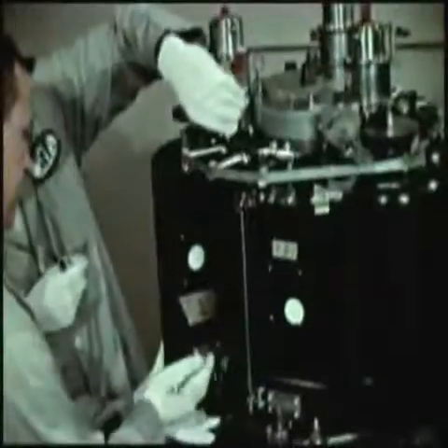Electromechanical control drum drive systems must operate at temperatures around 1,000 degrees Fahrenheit and will see radiation doses estimated to be 10^19 NVT of fast neutrons and 10^11 rads of gamma radiation. Control drum locations must have maximum position reproducibility and minimum accumulated error through the entire operating range to meet these requirements. Alternate actuator and drive concepts are being developed in parallel efforts.